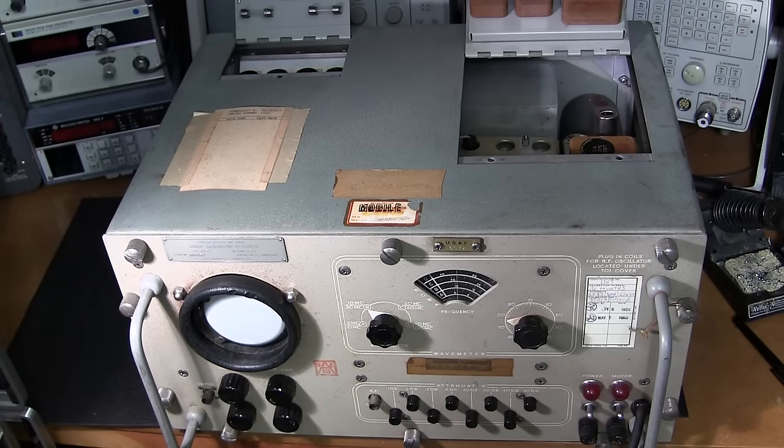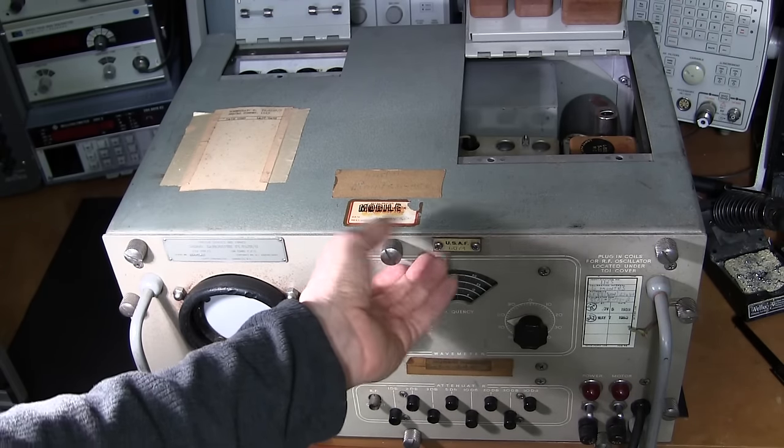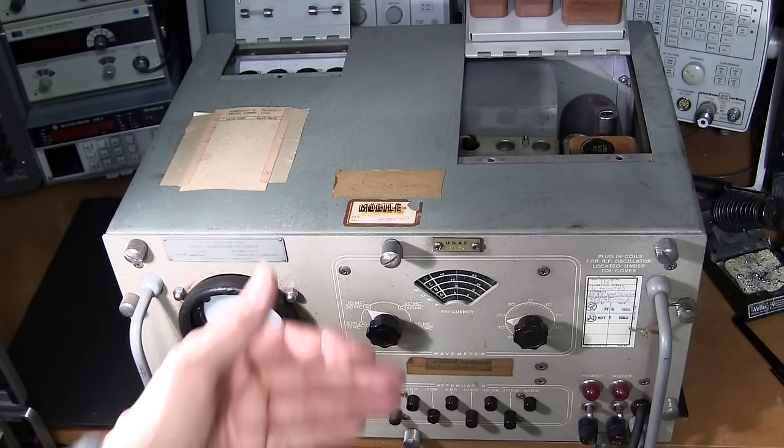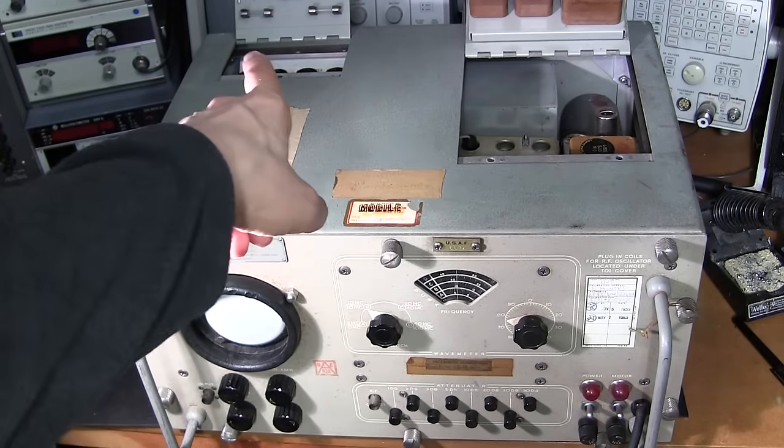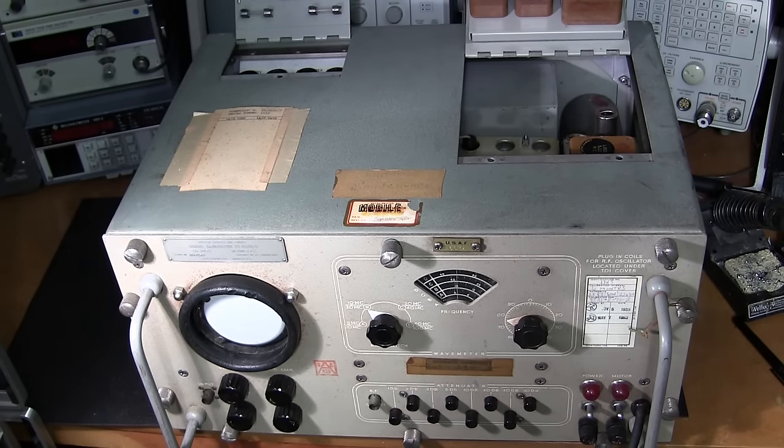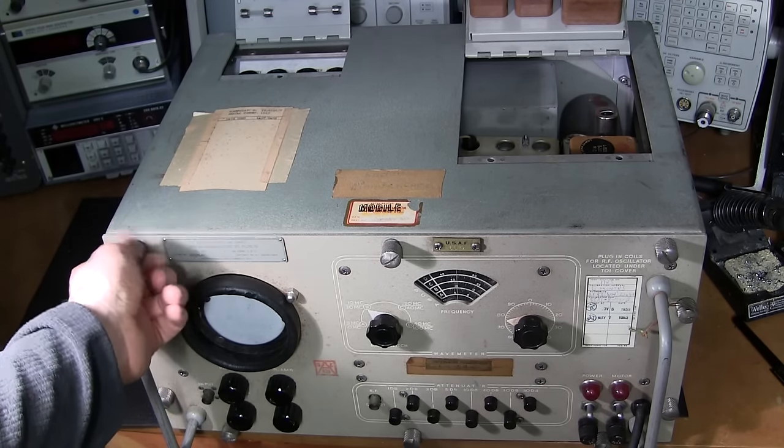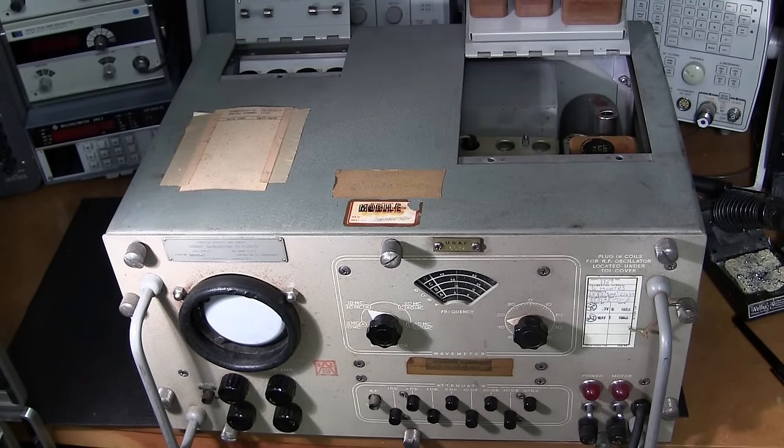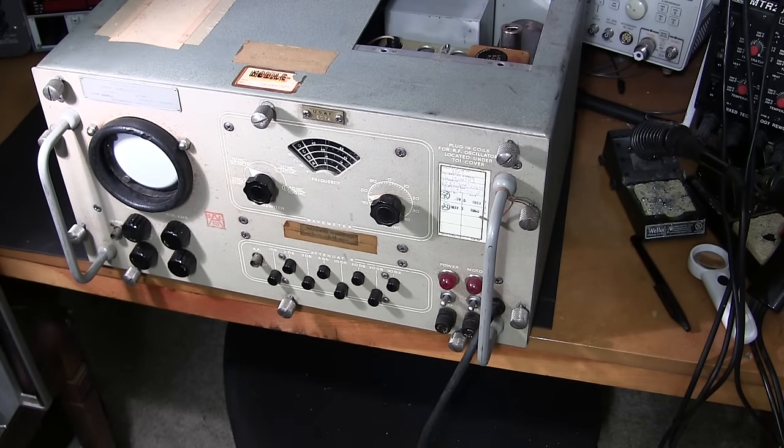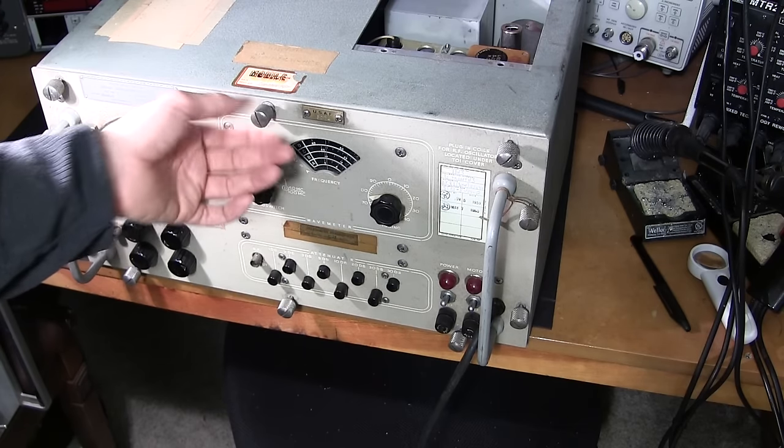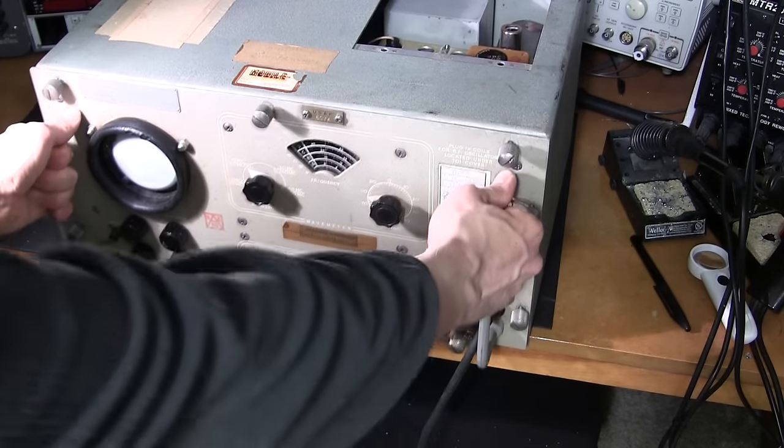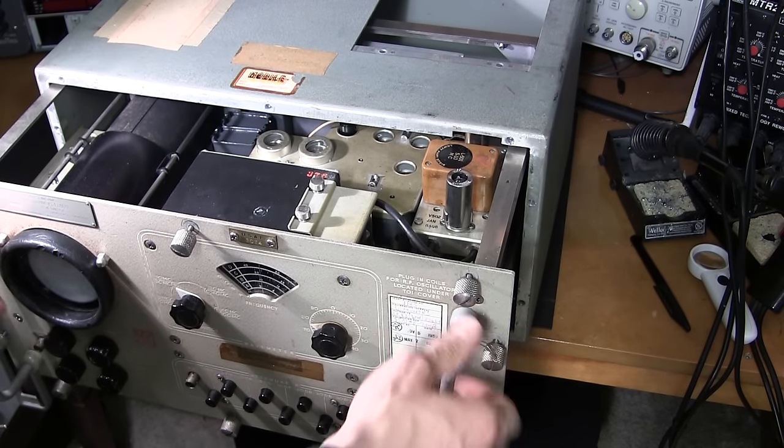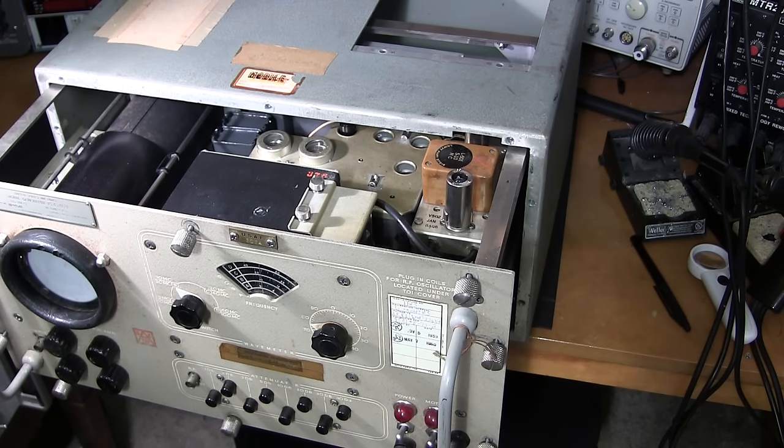In order to get this out of the case it's got these really large thumb style screws, so basically all you do is unscrew these for very easy servicing and this whole unit will slide out of the case. These doors will have to be left open or what's inside would catch on those doors. So what I'll do is remove all of these thumb screws here and remove the case and we'll take a look inside. The thumb screws are all loose, you don't have to take them completely out, just unthread them until they dangle in the hole and then you just pull the chassis forward and the whole thing is ready to come out of the case.